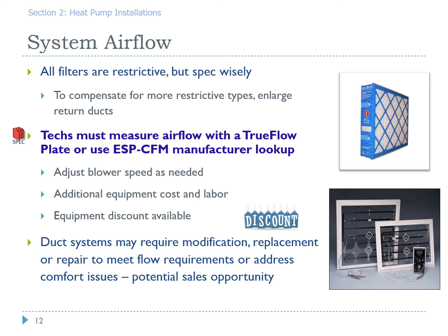But the ability to measure that airflow gives us the option to be able to adjust that blower speed to really dial in and meet that 325 to 500 CFM per ton specification. And then also you can think about additional equipment cost and labor that can be included into the bid. You know, modifications to ductwork to address system comfort and be able to meet the airflow requirements. You know, you can think of that as a sales opportunity.